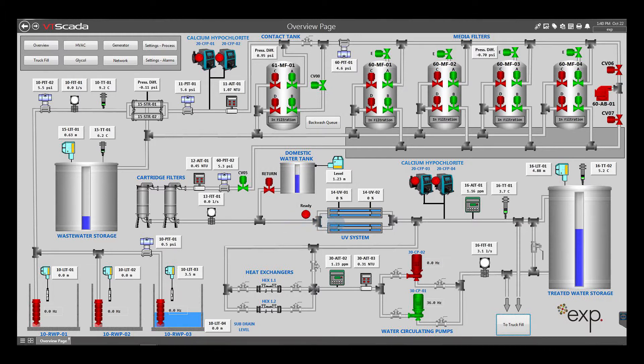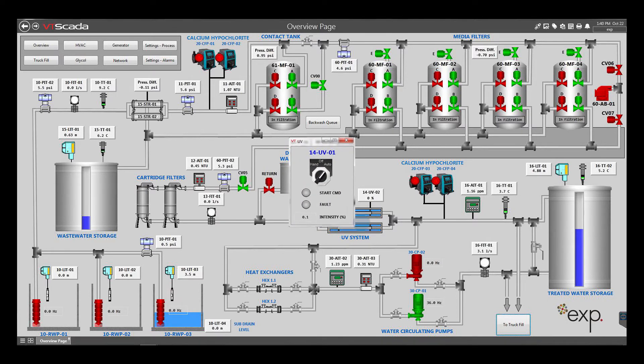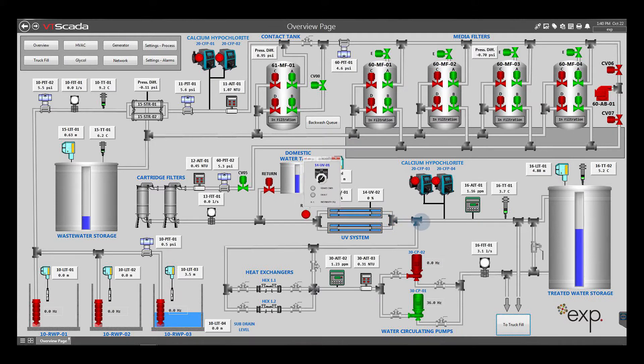The filtered water is sterilized by the UV lamps. The lamps indicate their transmissivity percentage; the minimum is 81%. The lamp has an automatic wiper that will clean the lamp sleeve every 2 hours, or as set by the manufacturer. When the lamp has been operating for about a year and a half continuously, it will signal that the operating time has expired and the UV lamp needs to be replaced.